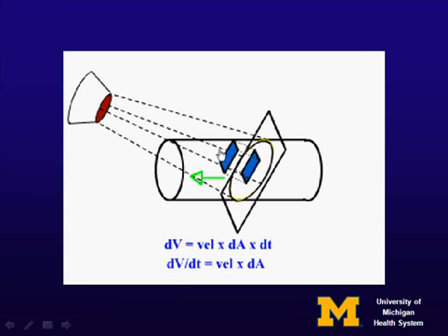Remember, this flow is now in the exact line of one of these rays from the ultrasound scan head, and that means that the Doppler shift you measure perfectly corresponds to the velocity of the blood at that point, which, remember, is exactly what we want. So now all we have to have is that area. We now have the velocity independent of angle at that point, and that's volume flow. So instead of having to correct all this stuff that we had to do in 1D with a 1D array, we now, using a 2D array, producing a 3D image, overcome the major problems that I talked about.